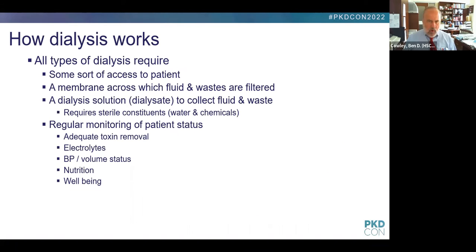All types of dialysis require some sort of access to the patient—we'll talk more about that in a minute—and a membrane across which water and waste products are filtered. I'll show you some diagrams in a moment. It also requires dialysis solution, what we call dialysate, to collect the waste products and fluid being removed. That dialysate is in very close proximity to the patient, separated only by the dialysis membrane, so we require very sterile constituents in the dialysate, sterile water and sterile chemicals.